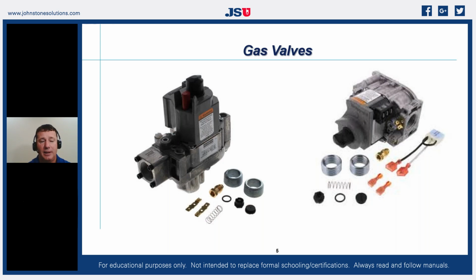If we talk about electronic ignition, hot surface ignition, we also have valves that are very flexible and very universal to replace some that we have in the brand, because typically we're only going to see Honeywell and White-Rodgers. That's really our two primary gas valves that we're going to encounter, especially with our equipment. So a lot of those valves are built on the same principles as far as manifold pressure and operating conditions. So the BTU capacity range is pretty broad on the valves that we use. So if we can keep a universal gas valve around, we're going to find that there's a lot of times we can use those valves to replace our existing gas valve, even if it doesn't look the same, doesn't fit quite identical, we can tend to use those to complete that job on that first time.